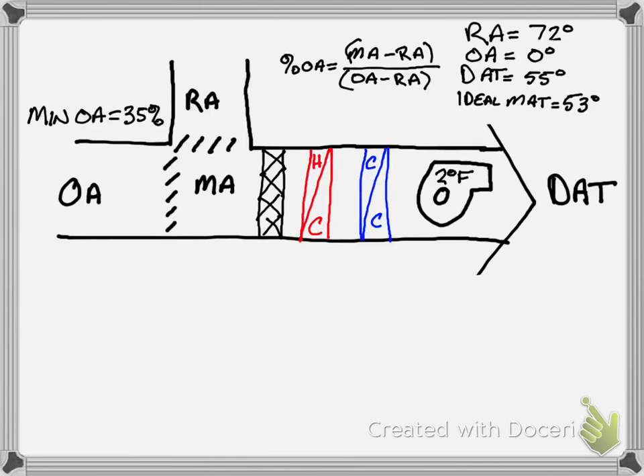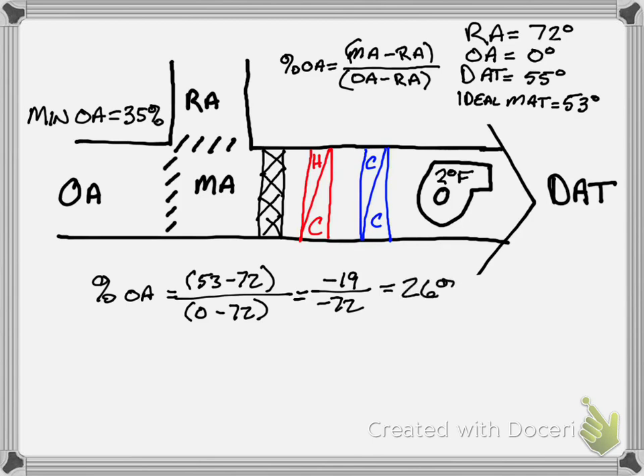So we go percentage of outside air equals 53 minus 72 over 0 minus 72, which comes out to be negative 19 over negative 72. So at least we have a negative on the top and the numerator and the denominator. And this comes out to be 26%.